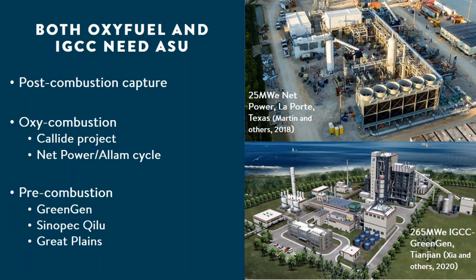As power generation moves towards net zero emissions and we think about how fossil fuels can be part of that journey, post-combustion capture, oxy-combustion, and pre-combustion are the three technology approaches to achieve that. The latter two both require oxygen. In oxy-combustion, the fuel is burnt in oxygen, and by eliminating the nitrogen, it makes the subsequent capture of CO2 following condensation of the flue gas relatively simple.